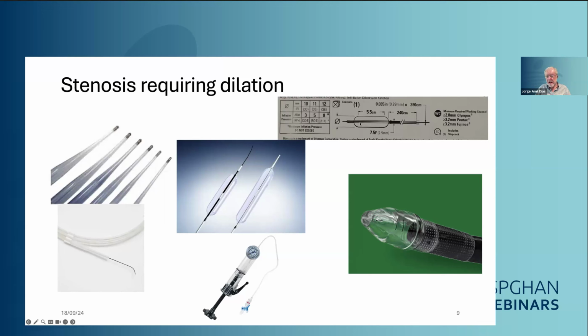And this table, which is in the package of each of these balloons, tells you which diameter you can achieve, how long it is, and the pressure that you need to use. Do not go beyond this pressure, because if you do, you'll just burst the balloon. And these balloons are inflated with water. So we fill the syringe with water, and then we create a strong pressure in the esophagus beyond the point of the endoscope.